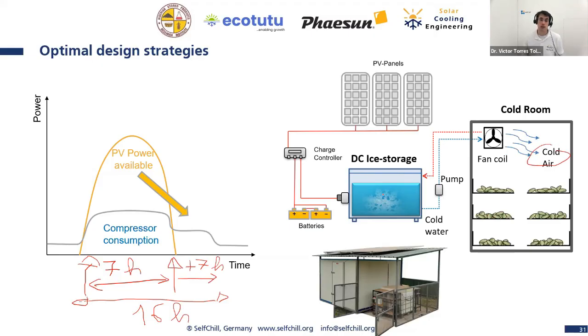So as long as you have ice, as long as you have cold water, you can deliver cooling energy. Even though the compressors are off, as you can see here, for between 6-8 hours per day, the compressors are not working at all, we can still deliver cooling energy through the thermal storage, through the ice storage. By the way, this ice storage that you can see in this diagram is this box here. Okay, so let's continue with this concept.